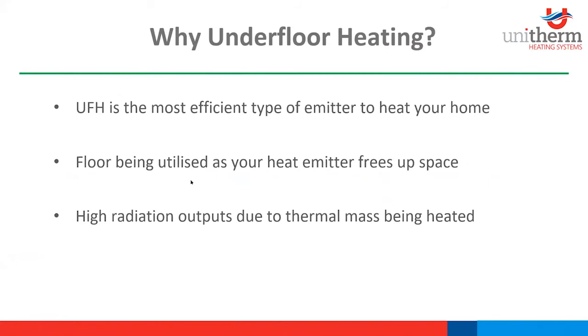So why underfloor heating? I suppose, as the floor is your emitter, as I said there a while ago, instead of traditional systems emitters such as rads, we now have a much larger area. So we can utilize a lower floor temperature. So the bigger the area, the lower the floor temperature we require. So the lower the floor temperature, then the higher the efficiency of the heat pump and the lower the running costs. The thicker the screed for the underfloor, the more thermal mass it will have and the more radiation it will produce. So that's what we're getting to here now.